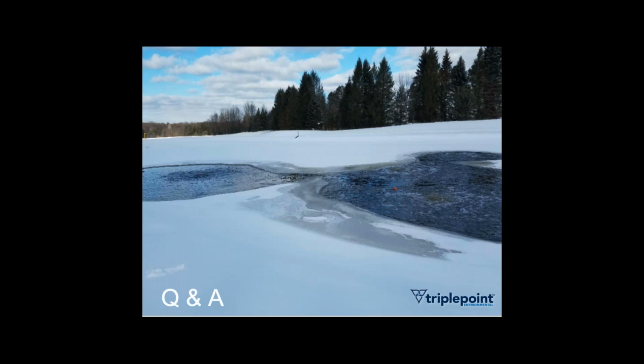What do we think about the possibility that the Aeries base will get stuck in the mud, making it difficult to remove the unit? It's possible. We do find over time that the units themselves will kind of get stuck down there, and we found that with the Mars as well. But if you use the proper equipment, you can pull it out. 9 times out of 10, that doesn't happen. There are occasions where, if there's a lot of sludge or different things down there, it's possible that it could get stuck, but most of the time we find that the units come up pretty easily out of the bottom.